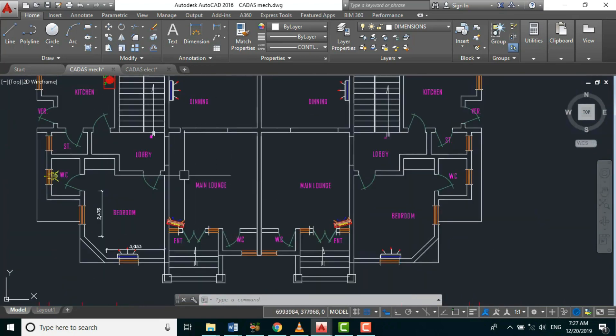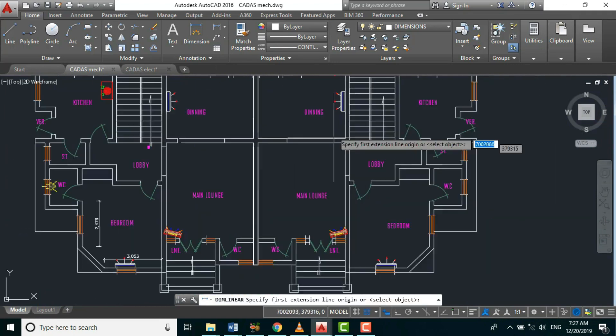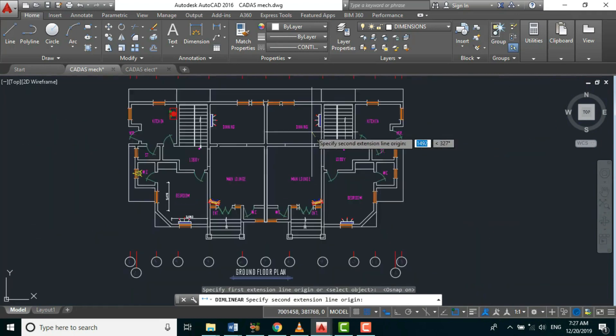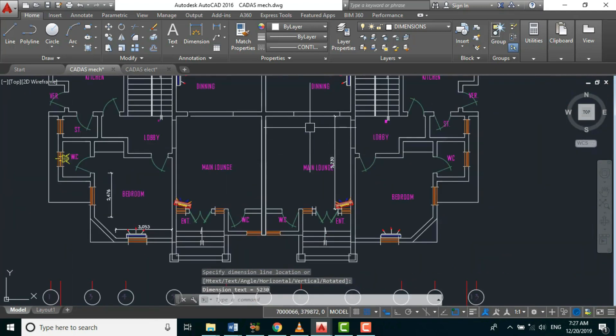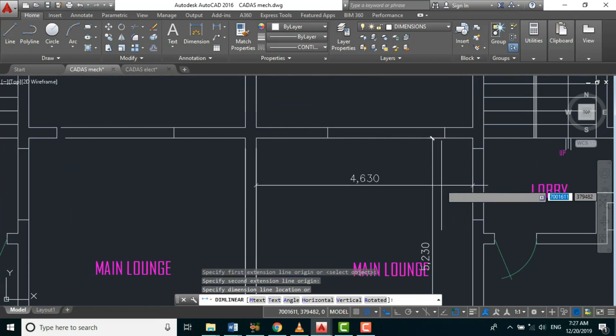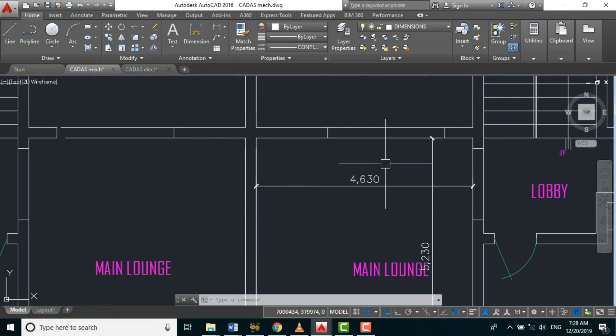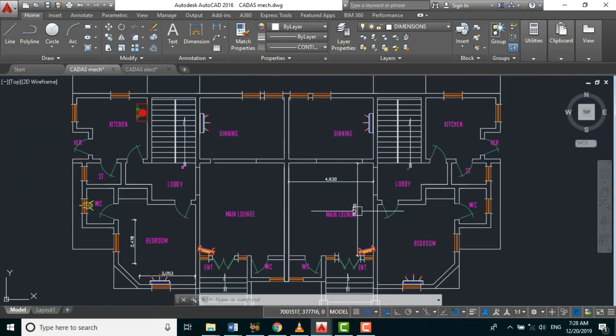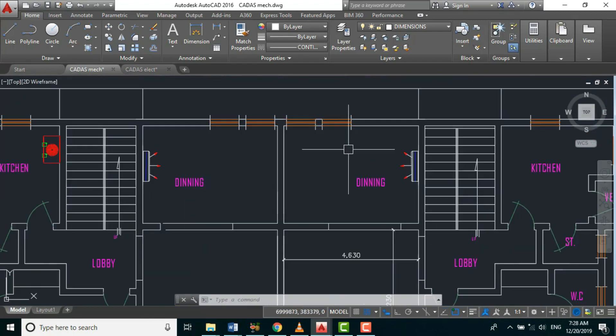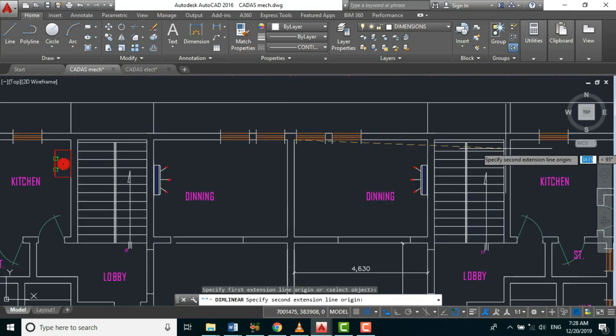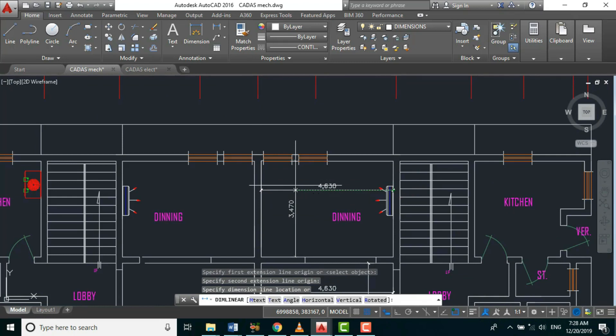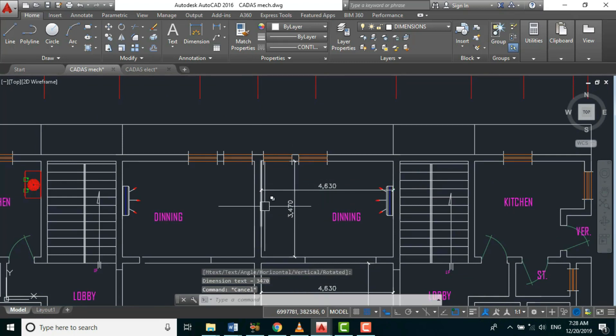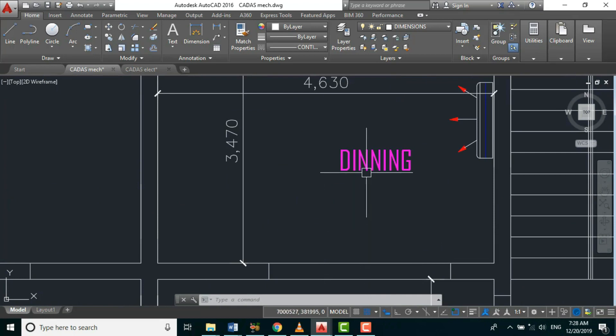For my main lounge, I'll use the dimension tool — that's 5.2 by 4.6, which is around 24 square meters. This means I'll be using 2 horsepower in the main lounge. For the dining area, the measurement comes to about 3.4, which is around 15 square meters, so I'll be using 1.5 horsepower in the dining.